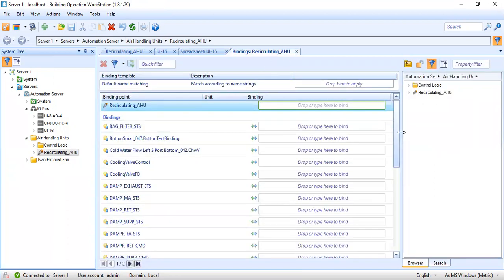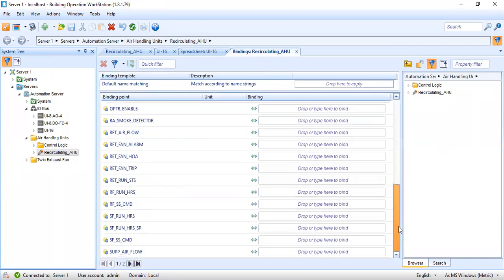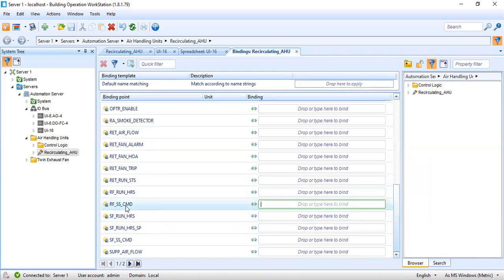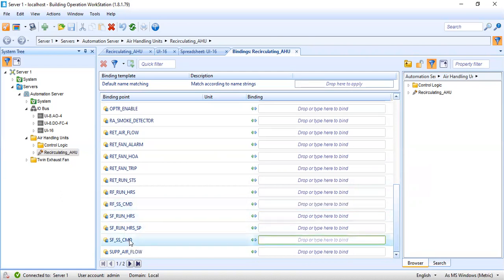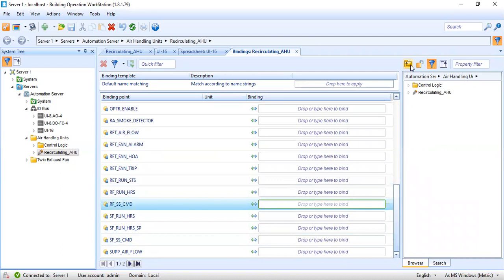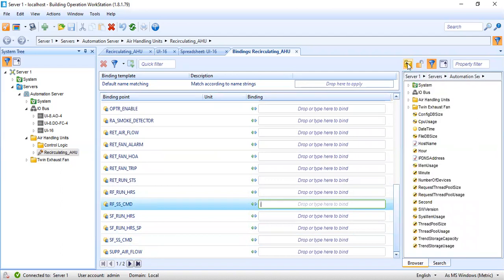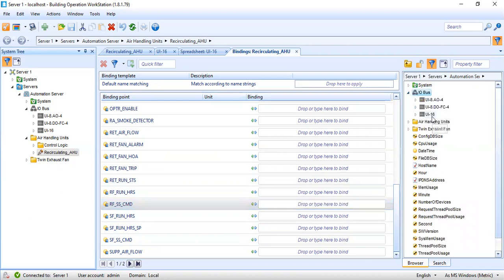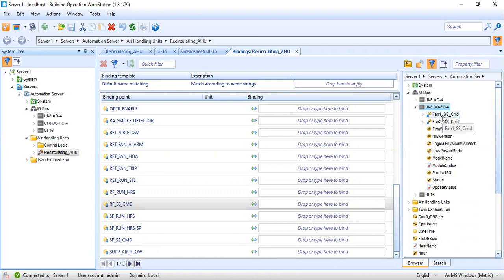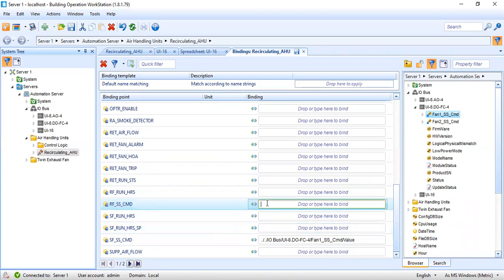In my graphics creation I used some object names. Here: return fan start/stop command and supply fan start/stop command. I will go here in my right window, go up directory, then go to IO bus where my IO modules are connected. The start/stop command are defined there. Fan one — as I said we will use it for supply — so I will drag and drop it to my supply start/stop command. Then I have my return fan start/stop command, so I will use fan two.